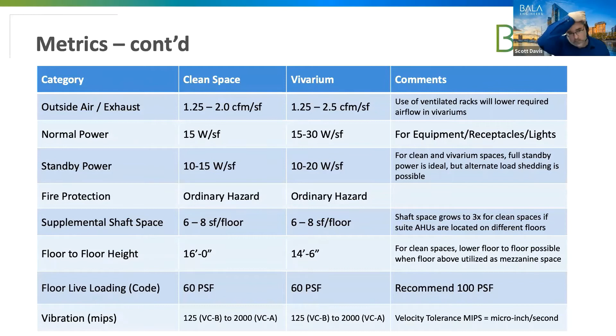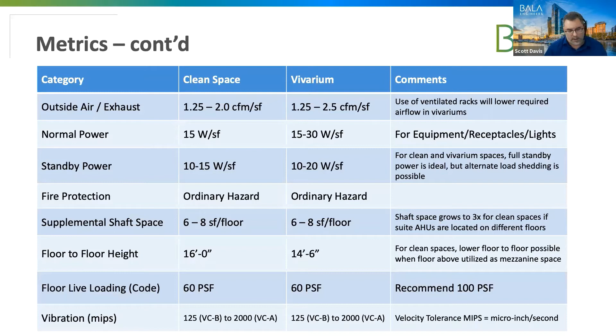In addition to that, it's also good to note that with clean spaces too, the HVAC systems want to be on standby power. With a lab environment, there are avenues where you just would run at a very low load just to maintain pressurization. When you're dealing with a clean space, now you're looking at potentially not just maintaining pressurization, but also temperature and humidity. Essentially, depending on how the room is validated, they may need to hold temperature and humidity even during a power outage. So again, just things to note when you're doing the programming phase, to fully understand what their needs are. But it's something you have to deal with, and again, a potential of additional extra power for the HVAC to operate at either reduced or full capacity.